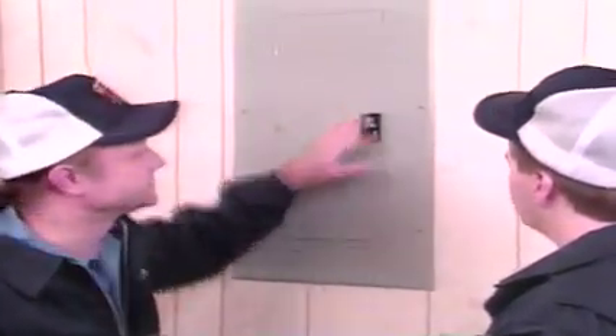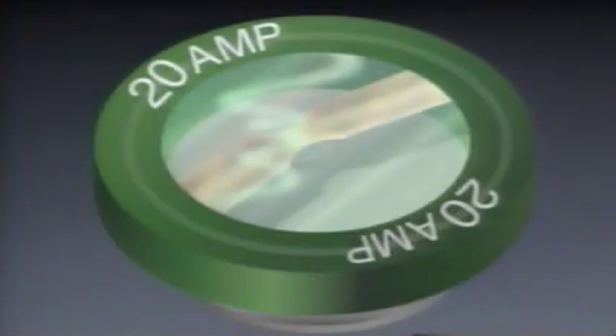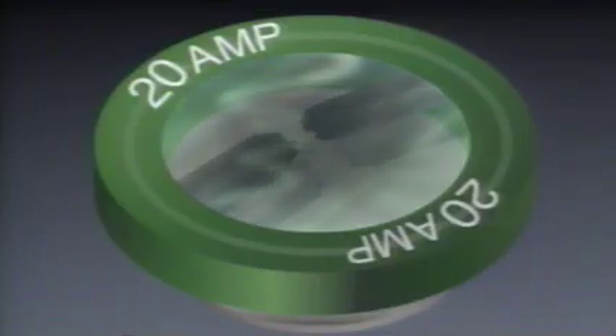Come on, let me show you something else. When using a fuse for protection, the electric current for each circuit passes through a thin, heat-sensitive strip of metal in the fuse before it enters the circuit. If the circuit wires protected by the fuse are designed to carry no more than 20 amps of current, a 20-amp fuse is used. If more than 20 amps flows through the metal strip in the fuse, the additional current creates more heat in the thin metal protective strip than it is able to handle. Thus, the strip melts, blowing the fuse, which opens the circuit. Electricity can no longer flow through the circuit.